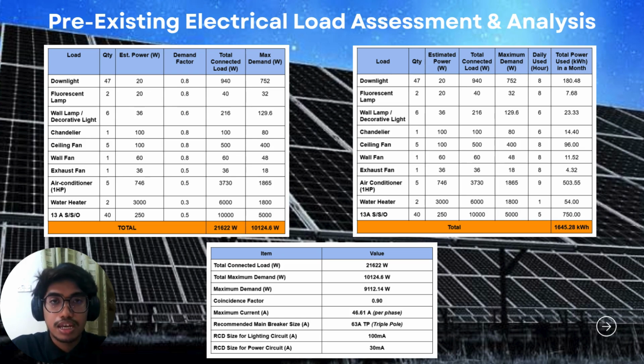So we can see the total connected load, total maximum demand, coincident factor, size of MCB, maximum current, and the size of RCD. I start with the maximum demand. The formula for the maximum demand is maximum demand equals total maximum demand times the coincident factor, which for residential is 0.9.